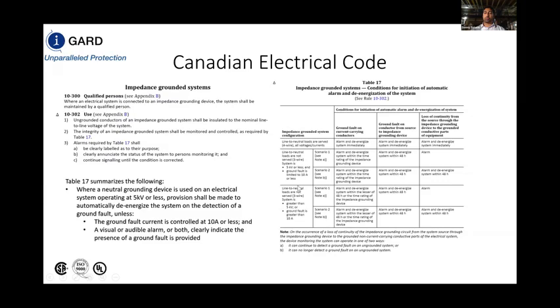Now, on this portion below, on the 3rd row here, it says that if you have a system that's greater than 5 kV, or if ground fault current is being limited to a value greater than 10 amps, then we have to alarm and de-energize the system within the lesser of 48 hours or the time rating of the impedance grounding device. But typically, consultants don't want that much wattage flowing back to their source.